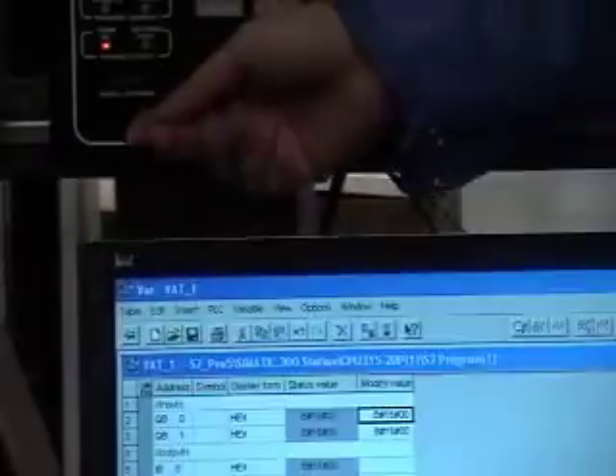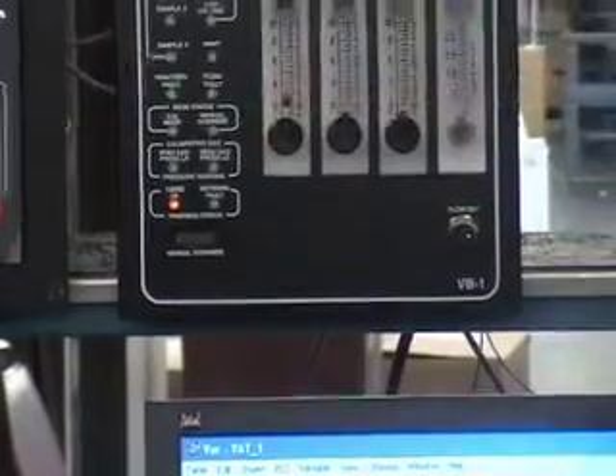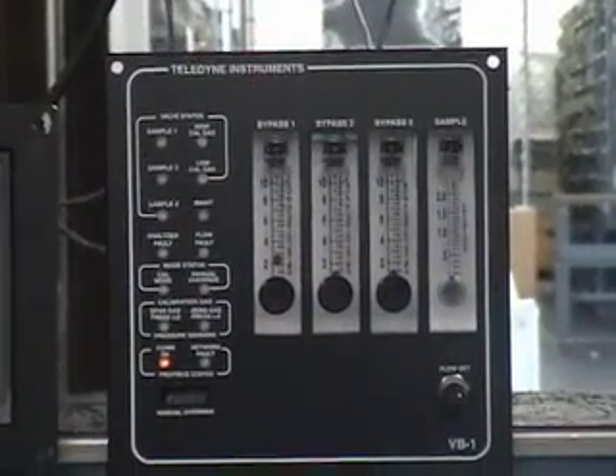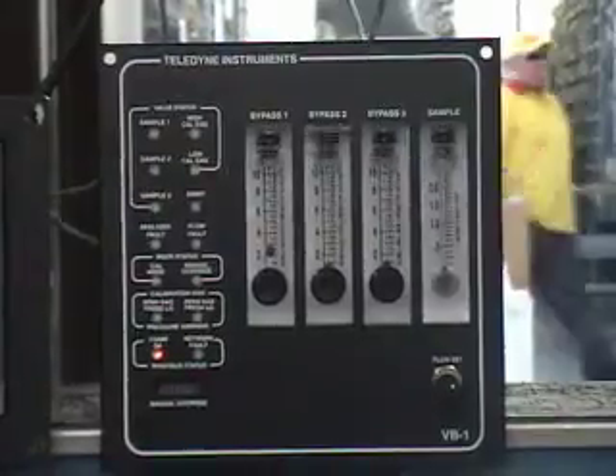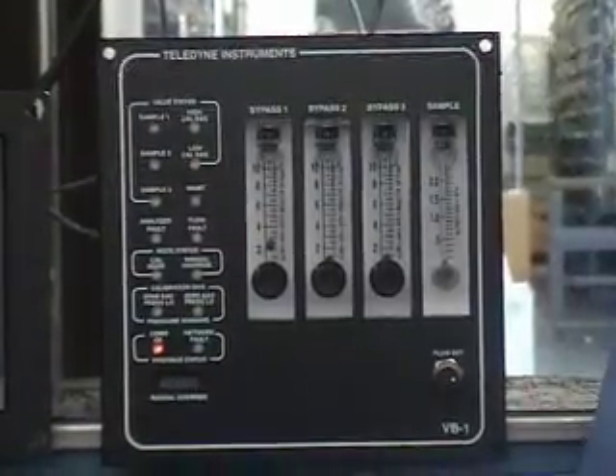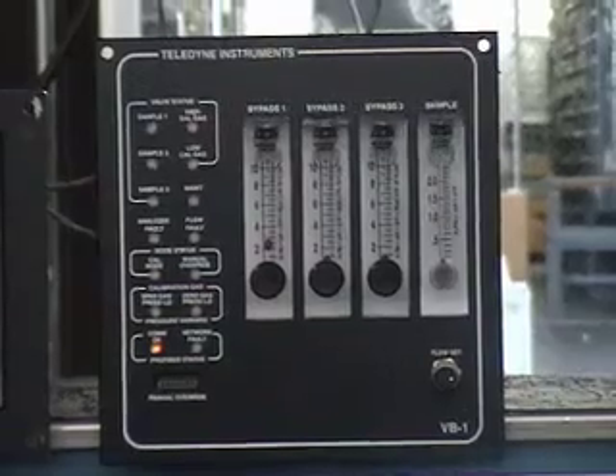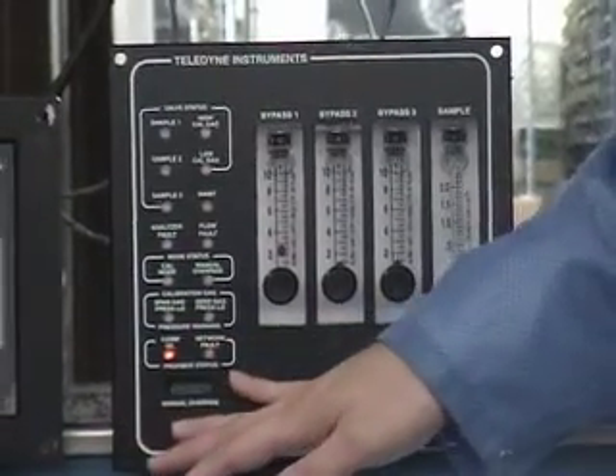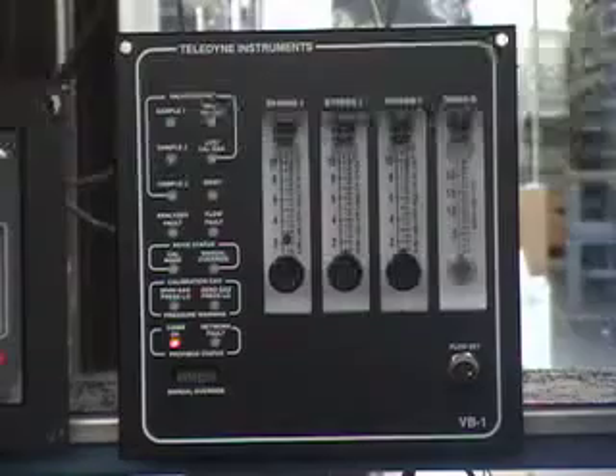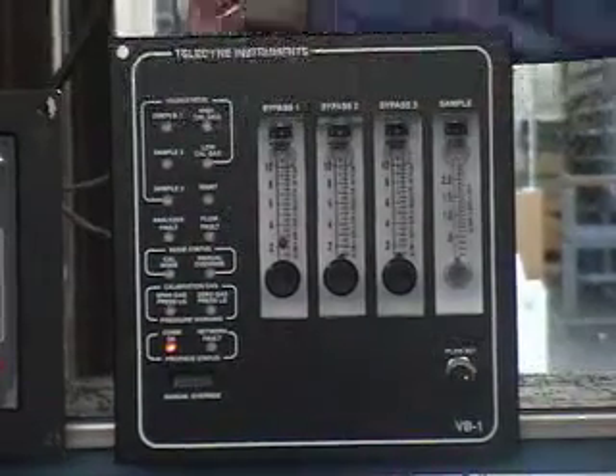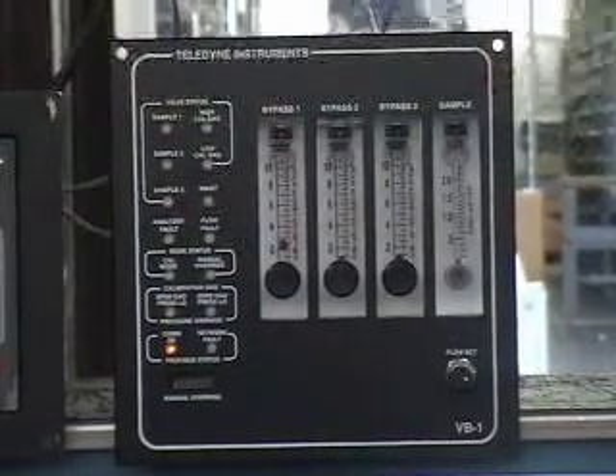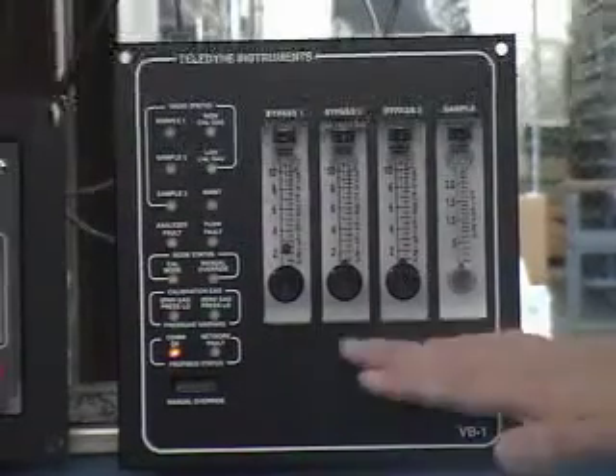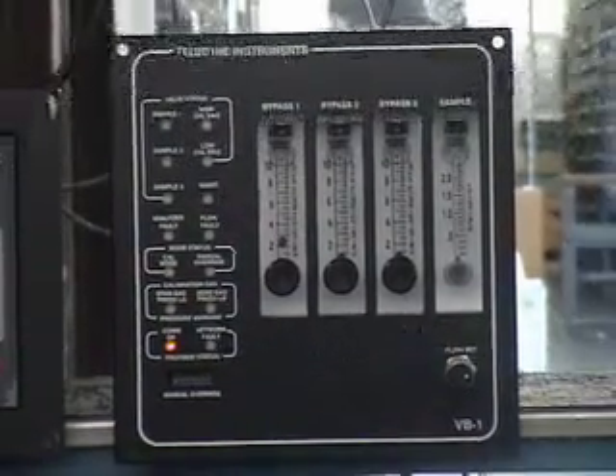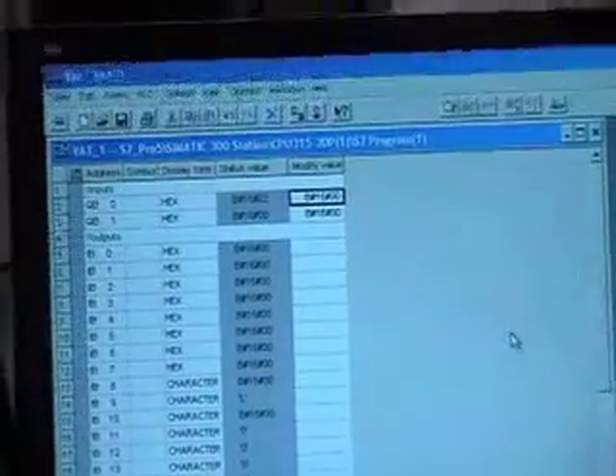Okay, right now the dip switches are all the way to the bottom. That means the VB-1 is under the control of the PC, of the Step 7 PLC, which means I can send commands through this computer. Right now it won't accept commands from the analyzer, and it won't accept commands from the back unless you set it up that way. So right now it's waiting for commands from the front, from Step 7. So we are going to go ahead and have the PC connect to the Step 7 PLC.